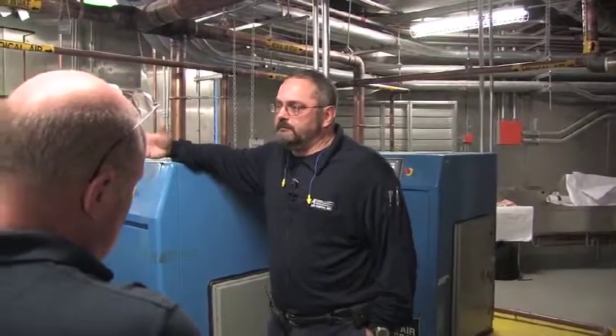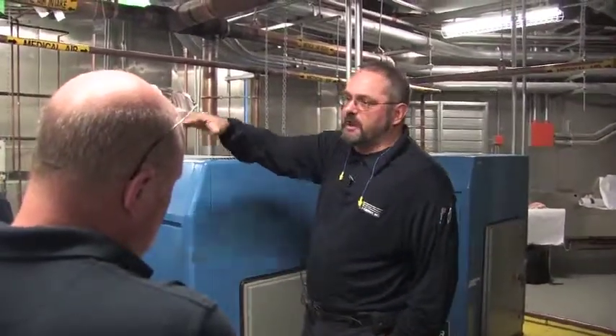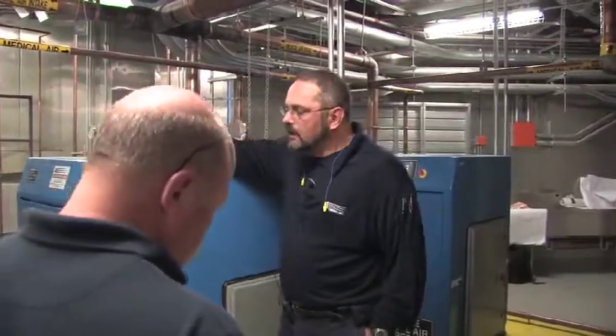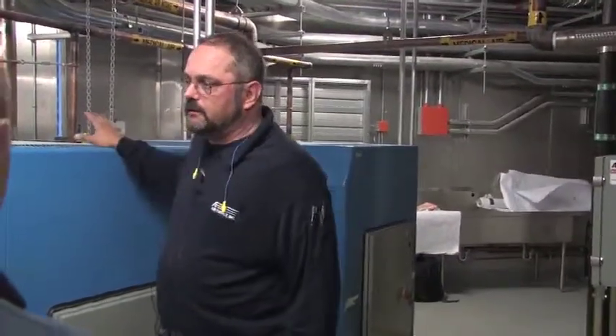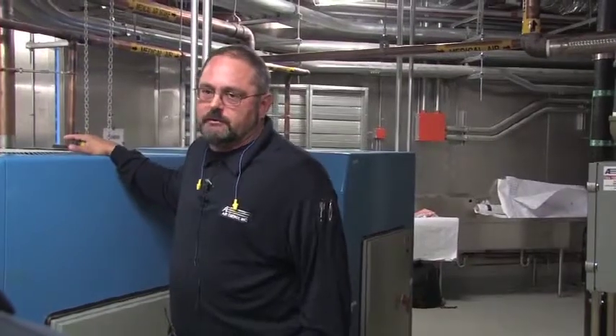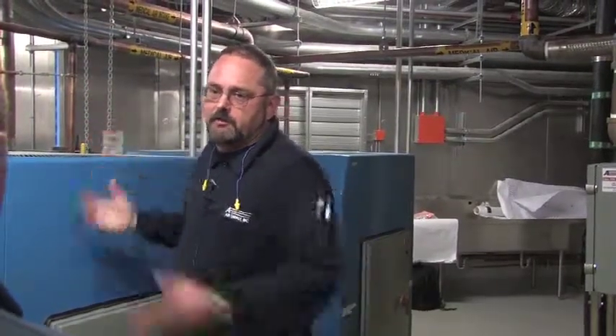So if we set them in three staggered settings, or if they're all programmed exactly the same, then they're all going to come on and off at the same time. So by having the lead-lag set up, if they get off the sequencer, they're going to operate either lead or lag depending on what they're set to. And if I remember right, what we did is we set number 1 with number 1 and 2 here with a lead and lag. So these two will switch between each other. And the third machine also has a lead-lag, but the settings are a little different. So in truth, you'll end up with a three-unit cascade depending on which one's lead and which one's lag.